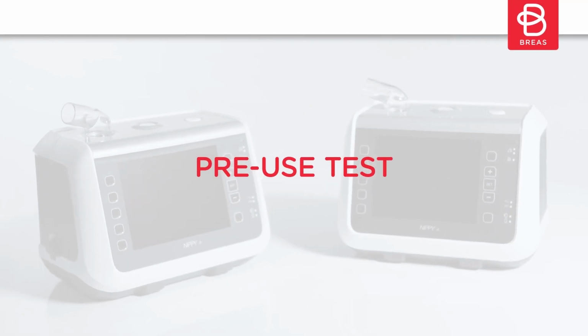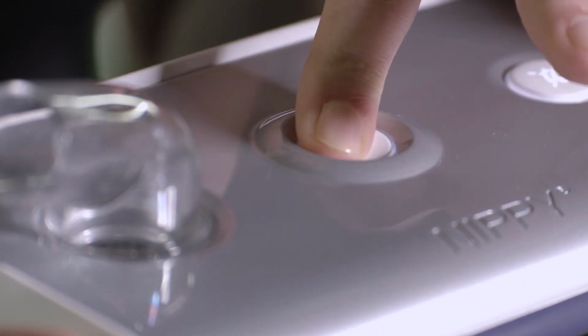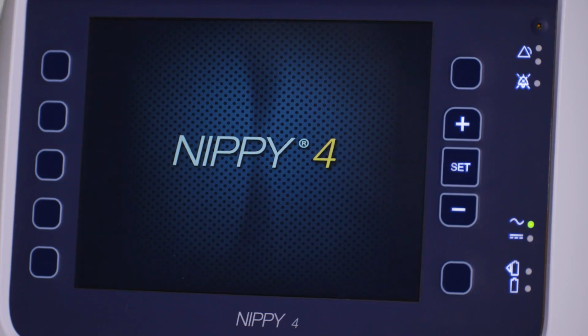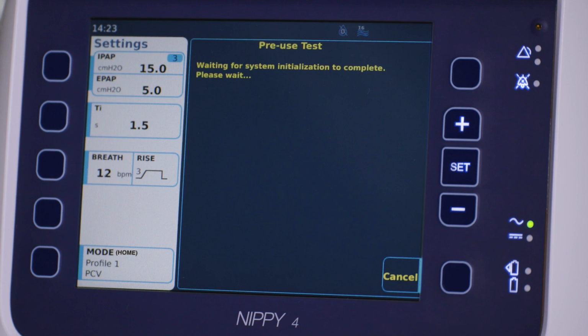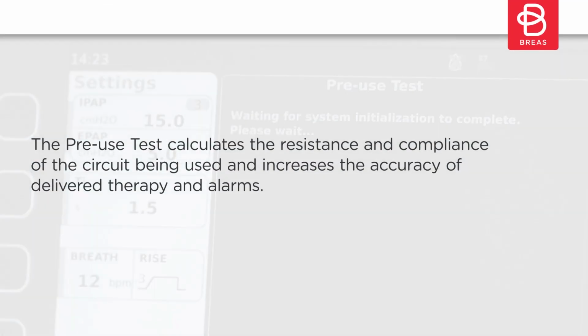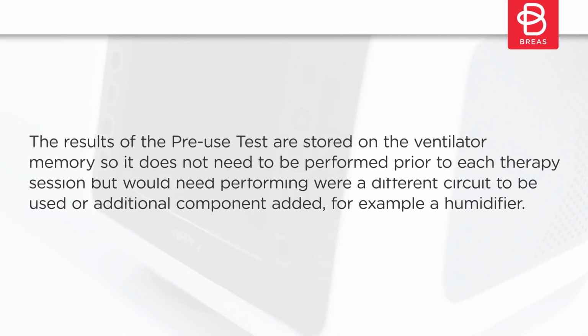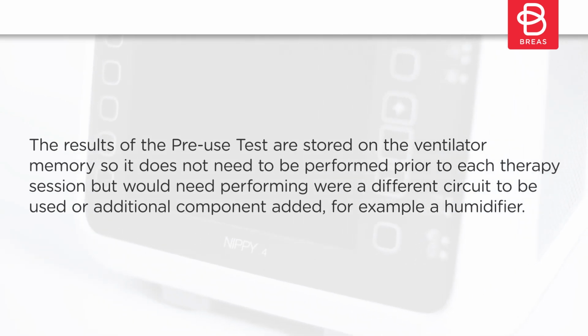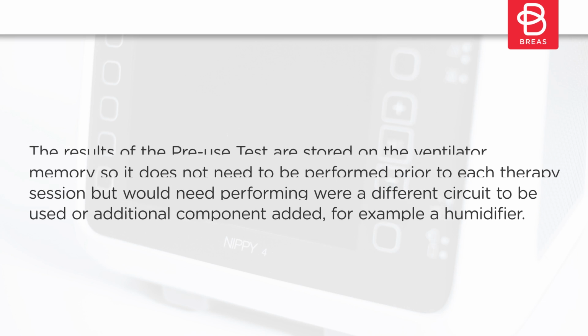Pre-use test. During the startup sequence, your clinician may have programmed your device to allow you to perform an optional pre-use test. The pre-use test calculates the resistance and compliance of the circuit being used and increases the accuracy of delivered therapy and alarms. The results of the pre-use test are stored on the ventilator memory, so it does not need to be performed prior to each therapy session, but would need performing were a different circuit to be used or additional component added, for example, a humidifier.